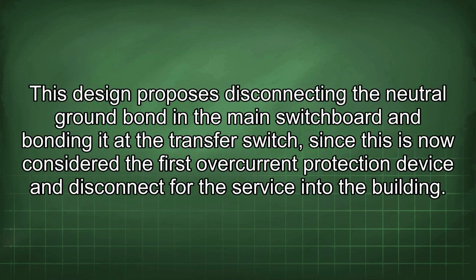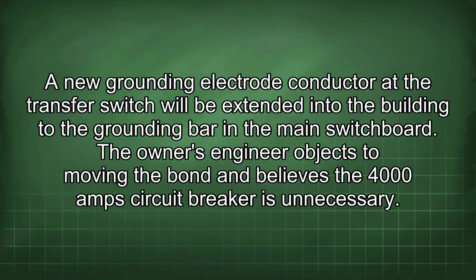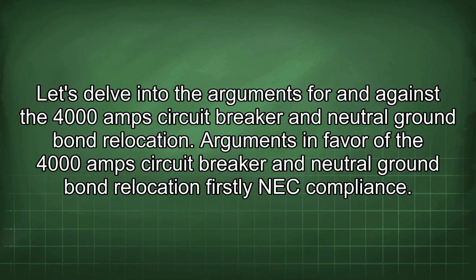This design proposes disconnecting the neutral ground bond in the main switchboard and bonding it at the transfer switch, since this is now considered the first overcurrent protection device and disconnect for the service into the building. A new grounding electrode conductor at the transfer switch will be extended into the building to the grounding bar in the main switchboard. The owner's engineer objects to moving the bond and believes the 4000 amp circuit breaker is unnecessary. Let's delve into the arguments for and against the 4000 amp circuit breaker and neutral ground bond relocation.